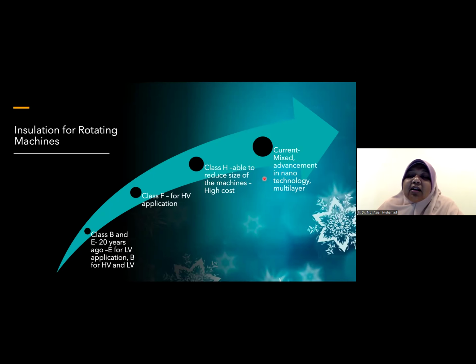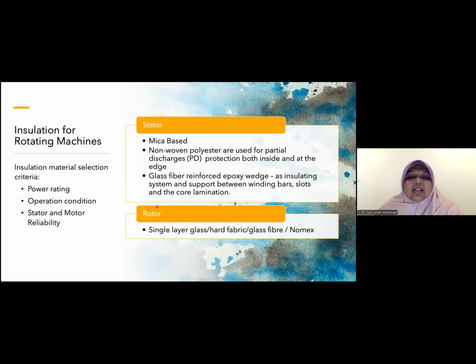And it's not that efficient. So now we are currently mixing them at once. We have nano, we have micro material, or a combination compound of insulation materials. So, like I said, in the rotating machine we have two parts: the stator part, the one that is static and does not move, and the rotor part, the one that is turning in the system. These two have different solid insulation material types.